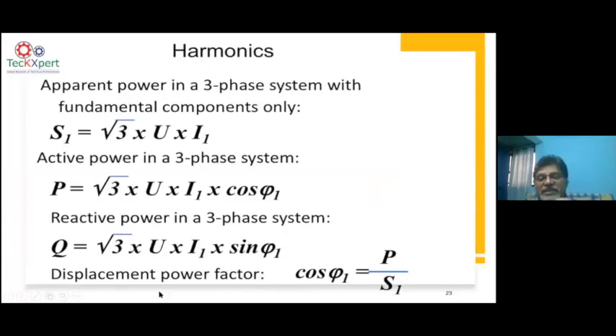Now, when there are harmonics in the system, harmonics also affect the power factor. Earlier I said power factor is the phase angle between voltage and current. In a perfectly balanced network, apparent power is √3 times voltage times current. Active power is √3 times voltage times current times cos phi. Reactive power is √3 times voltage times current times sin phi. This is how we calculate apparent, active and reactive power. Displacement power factor, the cosine of the phase angle between voltage and current, is a direct calculation: you divide active power by apparent power and you get cos phi.